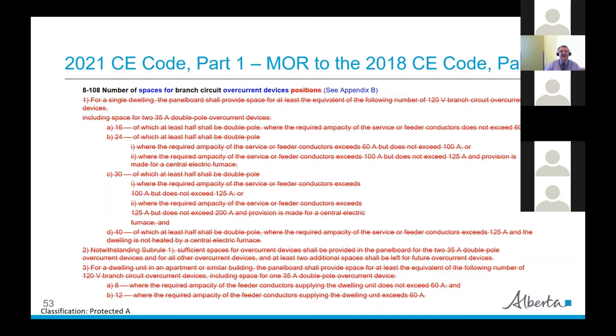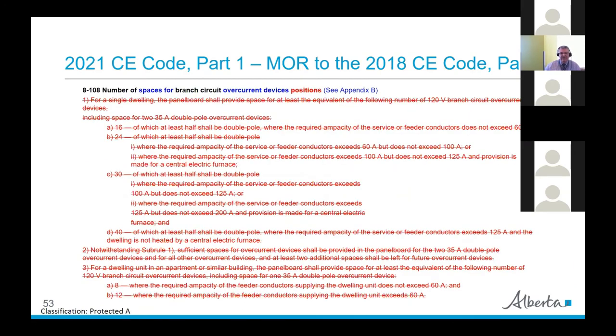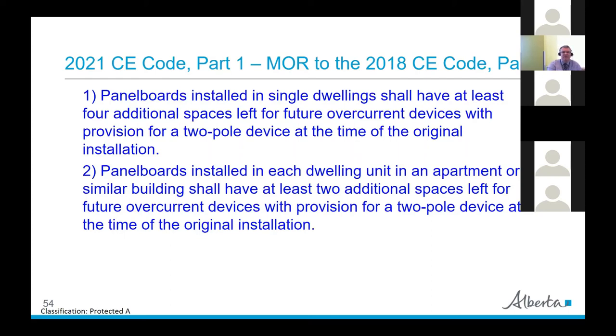In Section 8, there's a change on the number of spaces for branch circuit overcurrent devices. It used to say 'number of branch circuit positions' but now it's 'number of spaces for branch circuit overcurrent devices.' Two new rules: panel boards installed in single dwellings shall have at least four additional spaces left for future overcurrent devices with provision for a two-pole device at original installation; panel boards in each dwelling unit in an apartment or similar building shall have at least two additional spaces for future overcurrent devices with provision for a two-pole device.